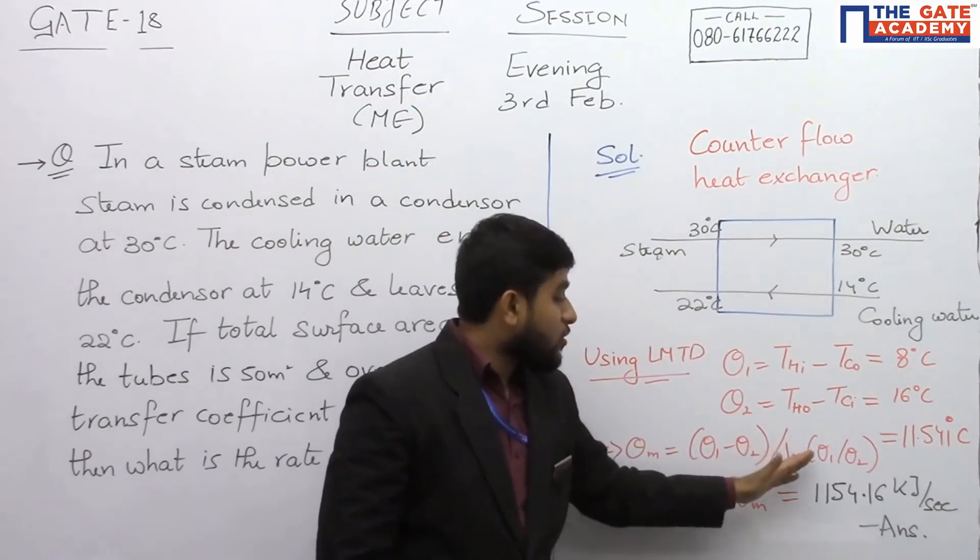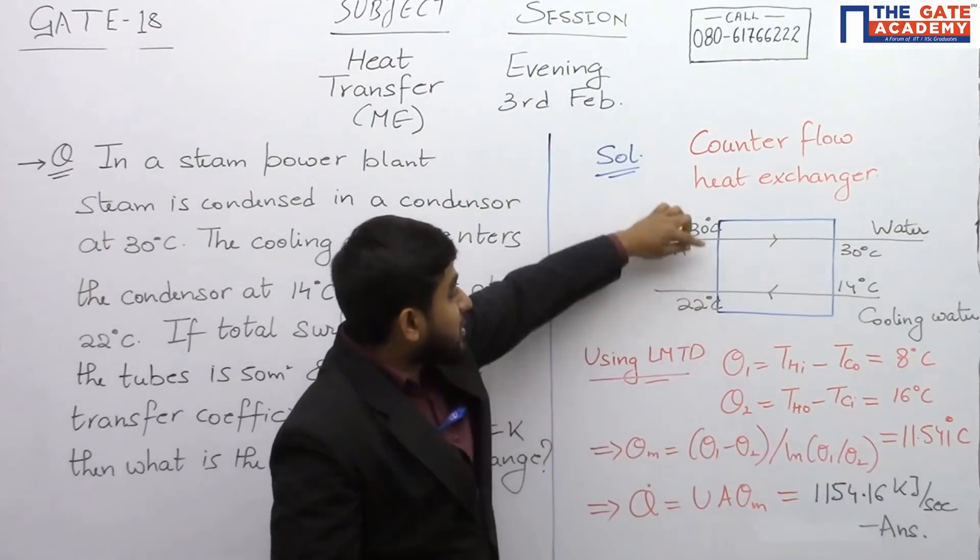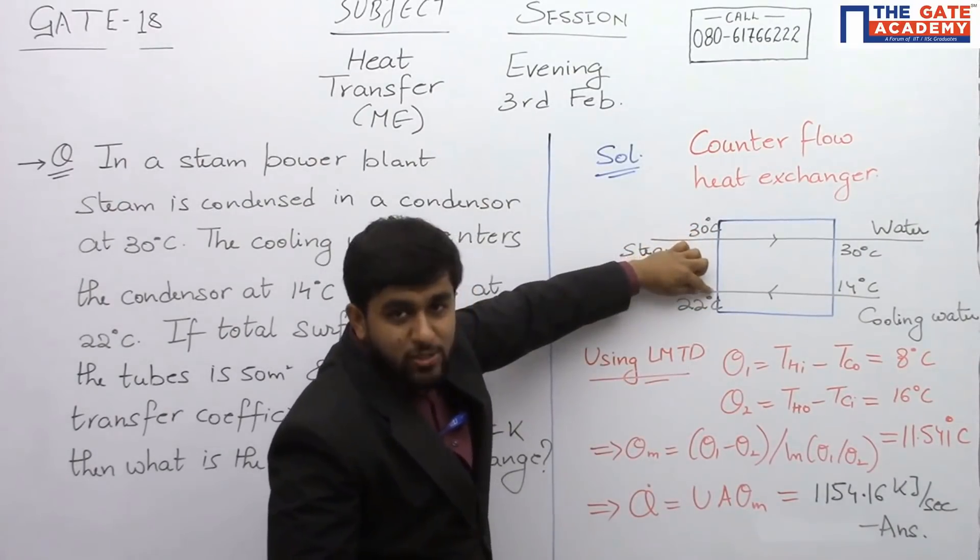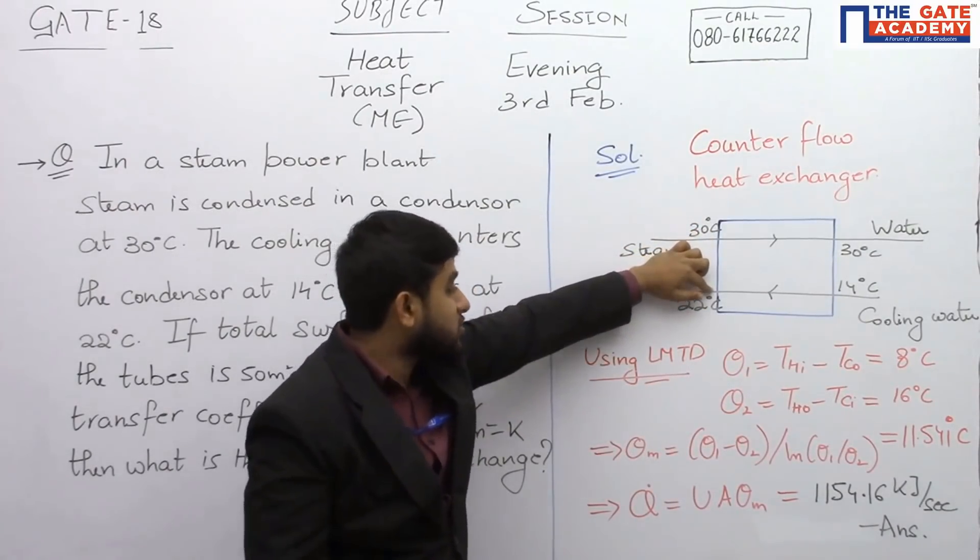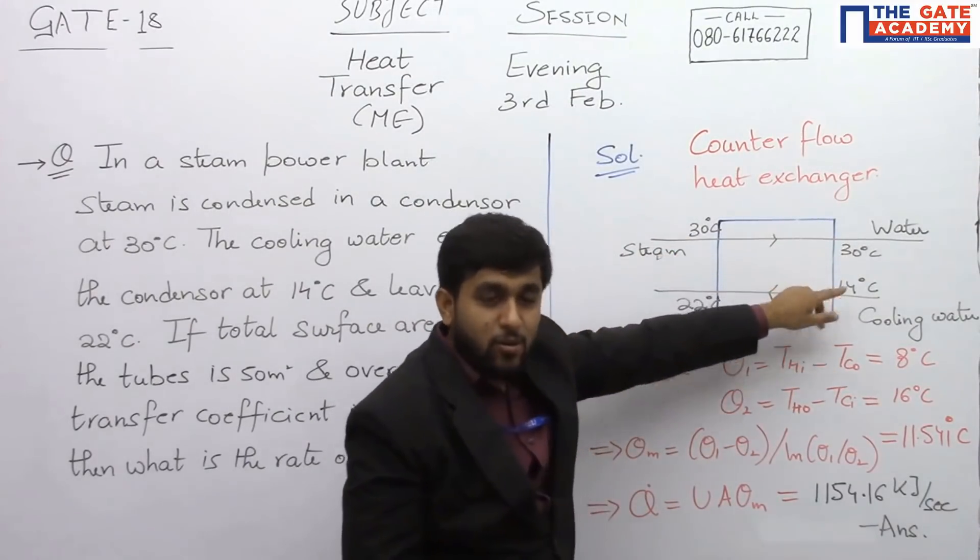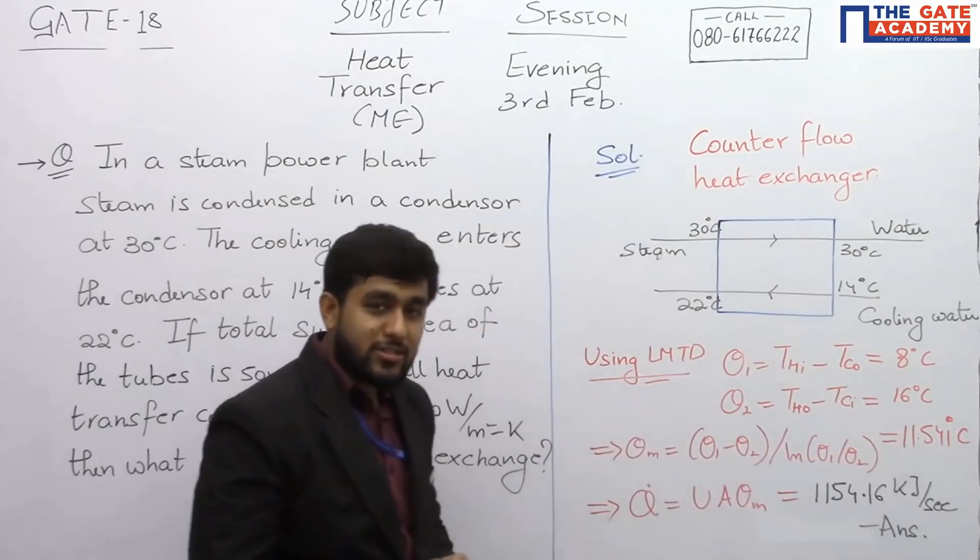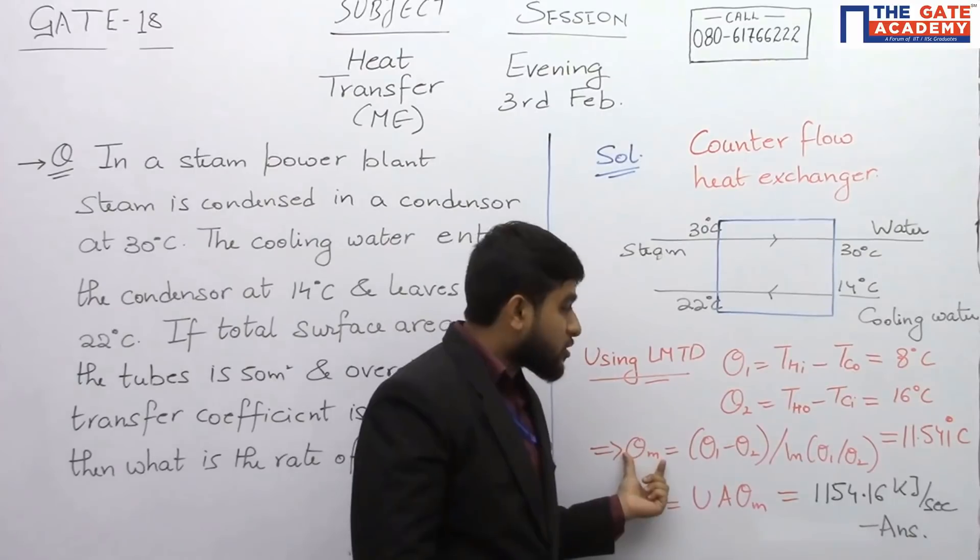What is theta one? Theta one is Th_i minus Tc_o since this is a counter flow heat exchanger. Theta two is Th_o minus Tc_i. Based on this, theta one becomes 8 degrees Celsius, theta two becomes 16 degrees Celsius. So logarithmic mean temperature difference, which is this, will be equal to 11.541 degrees Celsius.